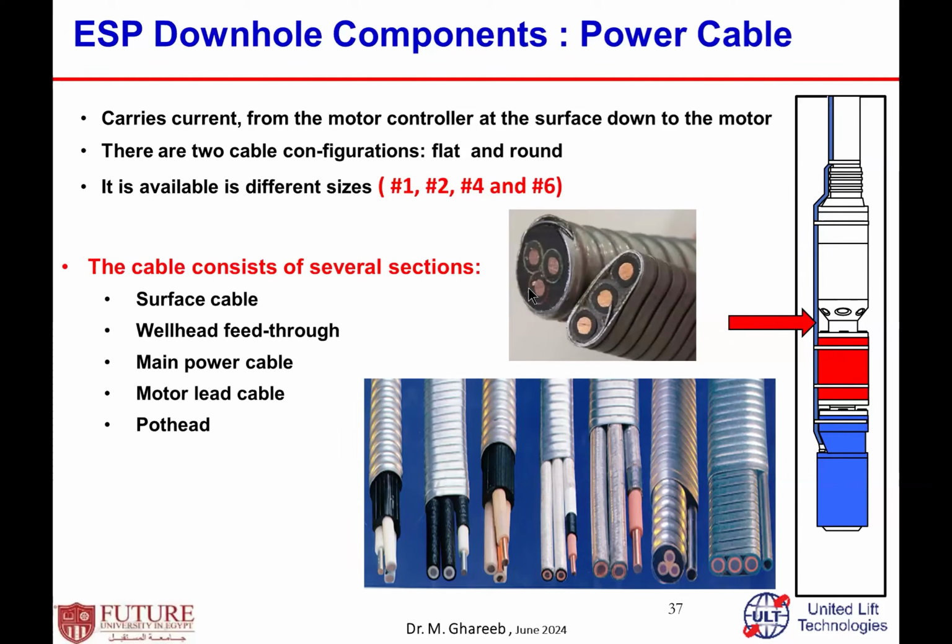What type of cable do I have to use in general, not only the downhole cable? I also have surface cable, wellhead cable, the main power cable in the downhole, and there is a special cable at the bottom hole assembly, starting from the pump up to the motor, called motor lead cable, and there is a connecting cable at the surface called potheads and so on.